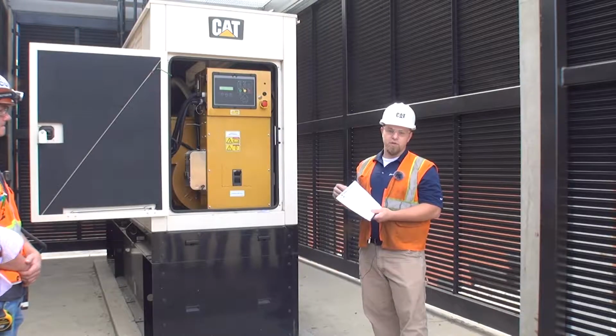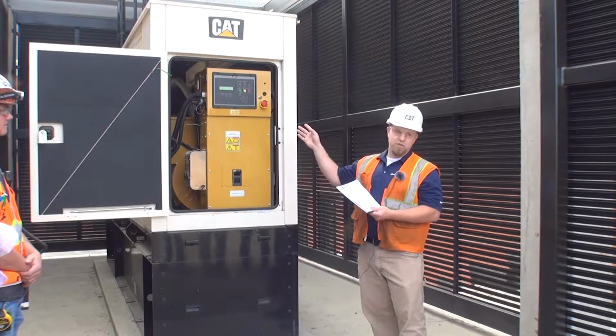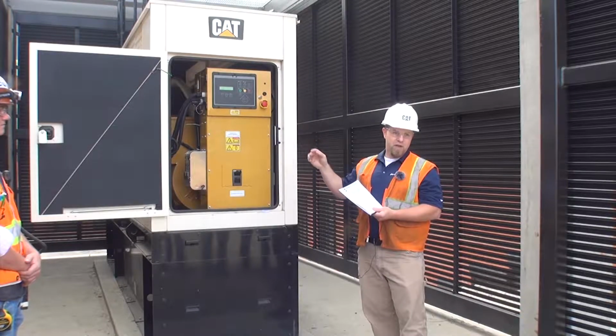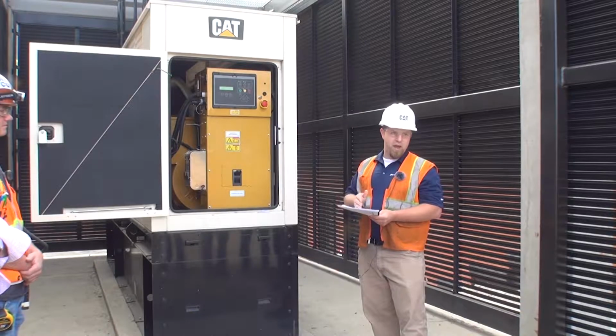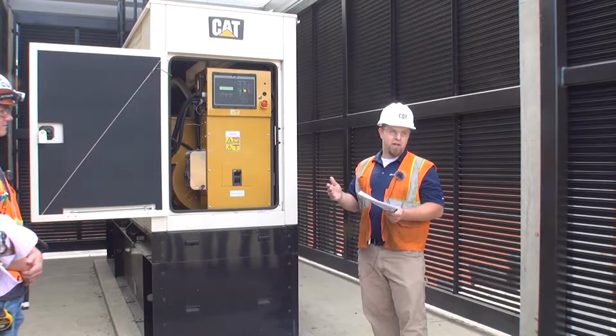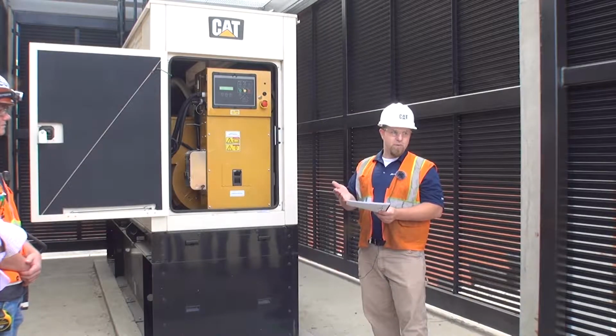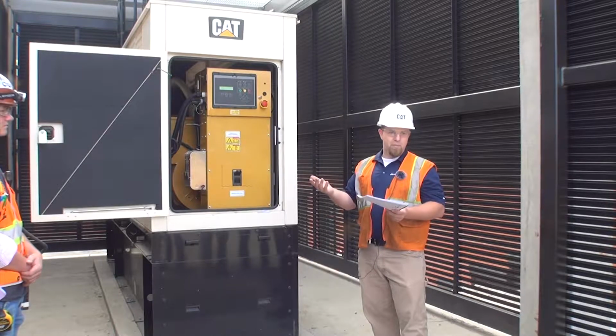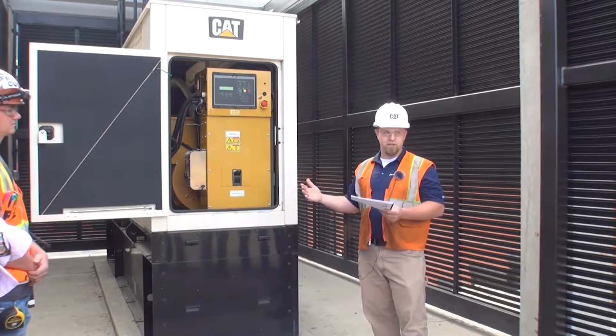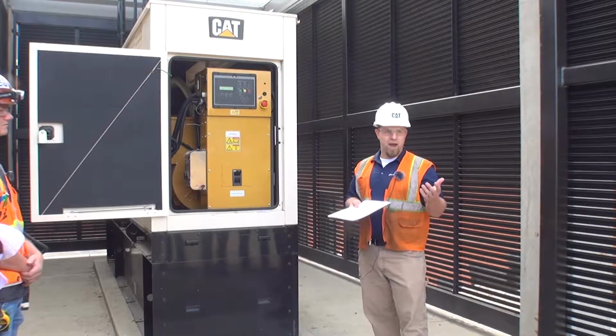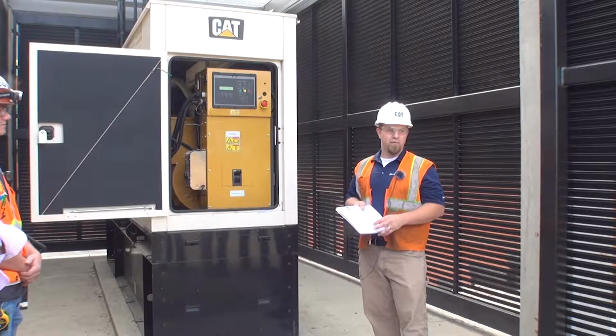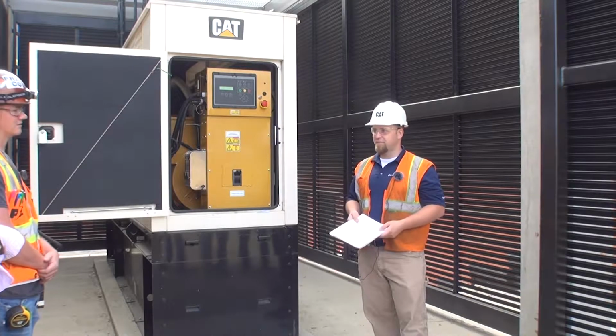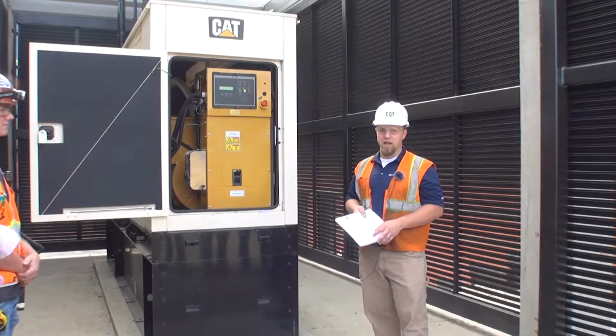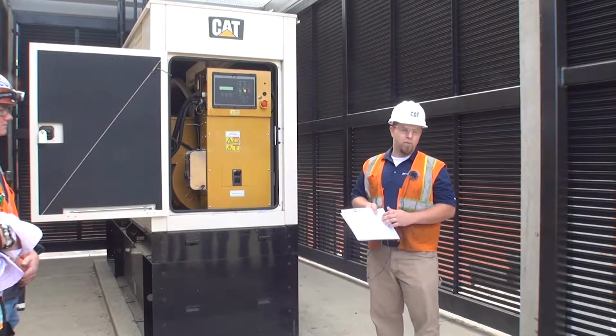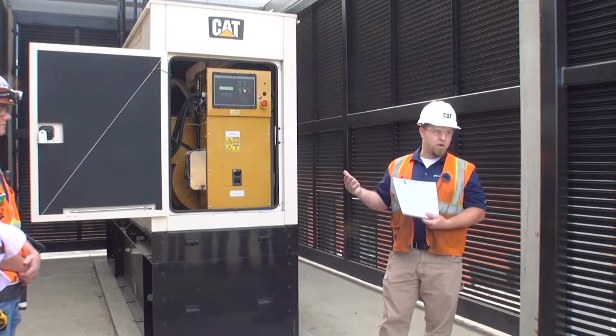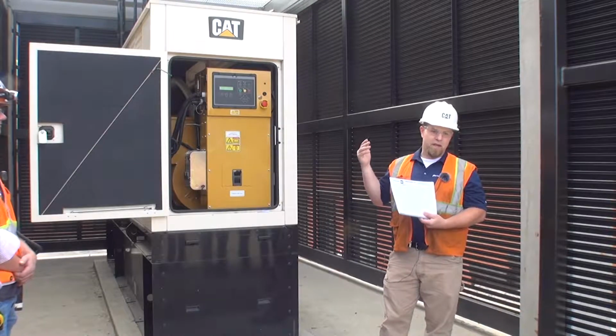What I recommend is when you're doing your monthly transfers or even your weekly, you start watching what your fuel gallons per minute burn is, and then also start tracking that over your annuals and your load banks and things like that, so you can start justifying in your head, okay, if I do monthlies, weeklies, and I do my annuals with the load bank at this much load, I'm going to need to fuel every 3 years or every 4 years. This isn't going to burn a lot of fuel. Unless you have a 5-6 day power outage, you're not going to be burning a lot of fuel with this, because I doubt the load is 10-15%. Yeah, it's very minimal. It's probably all LED lights. Very, very low load on this. What we always try and spec all of these to is full load, 24-hour runtime. That's a really good rule of thumb.